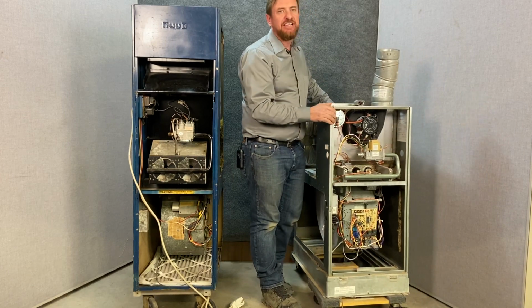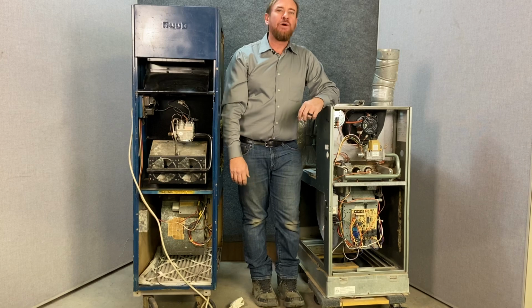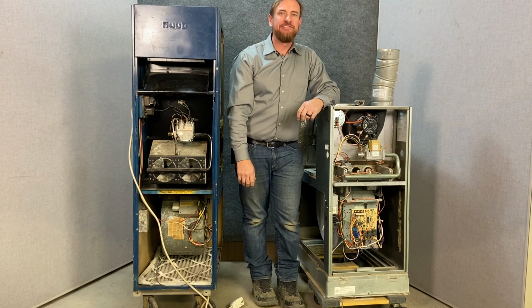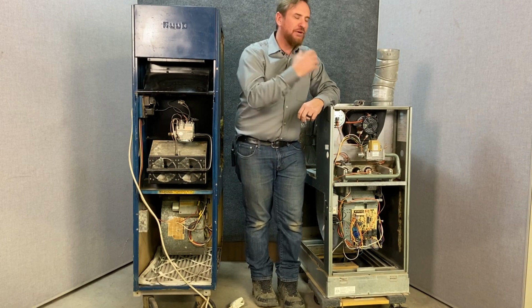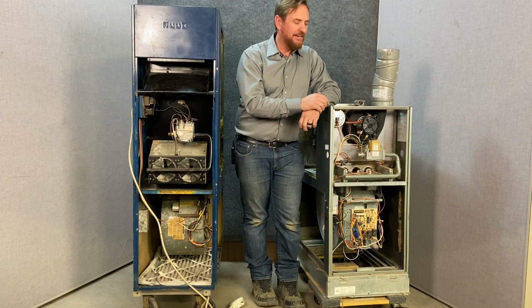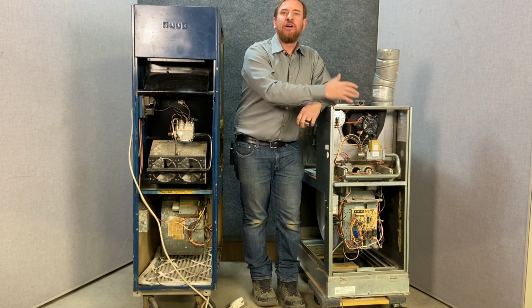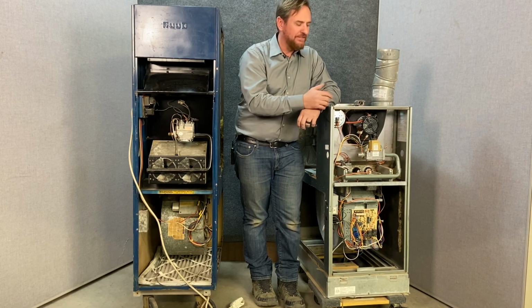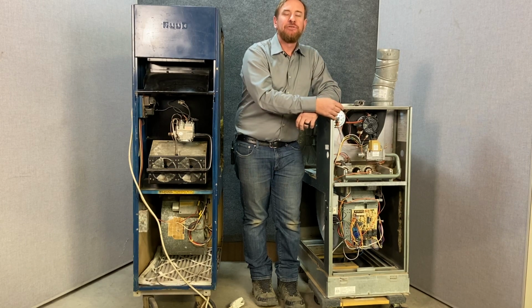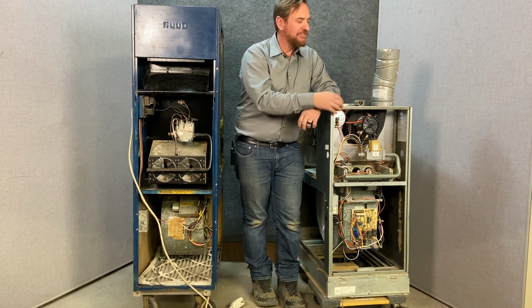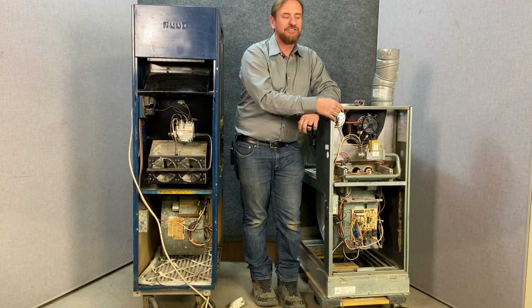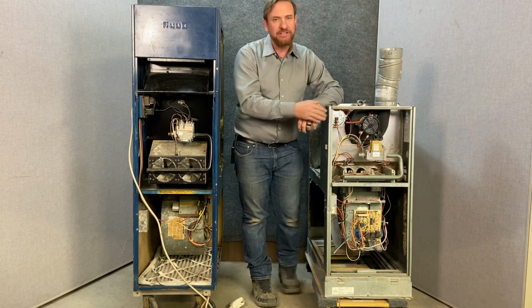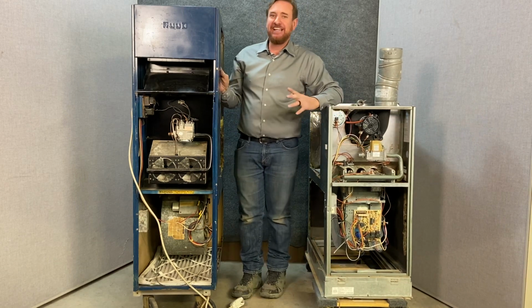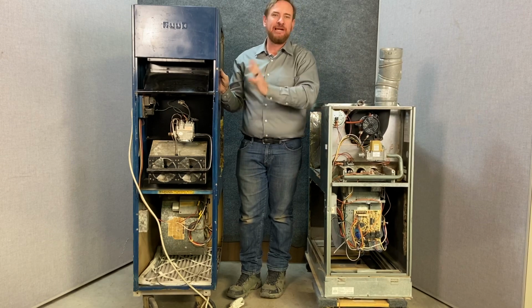The new furnaces now for the Northeast are required to be 90+% efficiency, condensing furnaces. We'll get one of those in a separate video and break that down. This furnace is still available all through the South and the Southwest. The temperatures don't get as low. You don't use the heating side, so they don't have as stringent of restrictions on those. But that's the difference between your 2 gas furnaces. If a customer's watching this, you got a standing pilot, it's time to upgrade, it's time to change it.